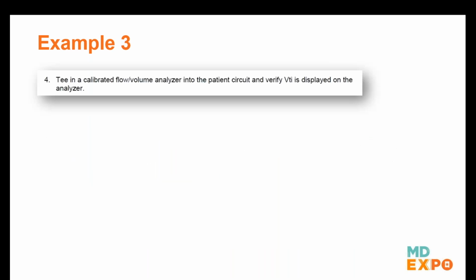Third example. And this is a great one. It just simply says, hey, tee in a calibrated test device, a flow or volume analyzer, and then make sure that it's able to display VTI. And it leaves it completely up to you on how to set that all up. So it's going to be very important for everyone to understand how their analyzer works. There's several out there, and we advocate for certain ones because we've been in the industry for a while. But the most important thing is that everybody understands what they all have in common and how each one is applied to these different test setups.